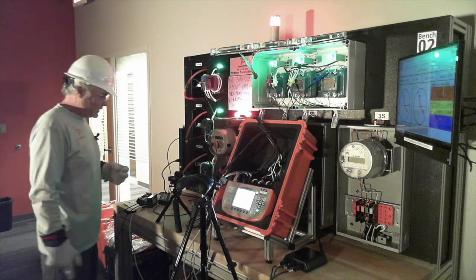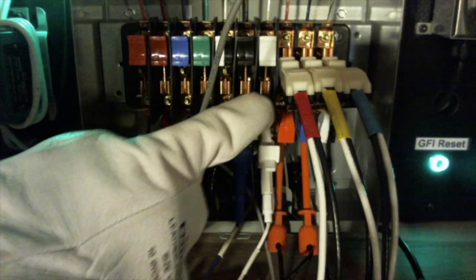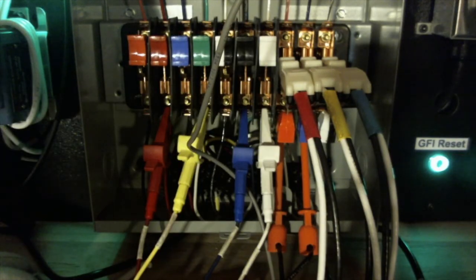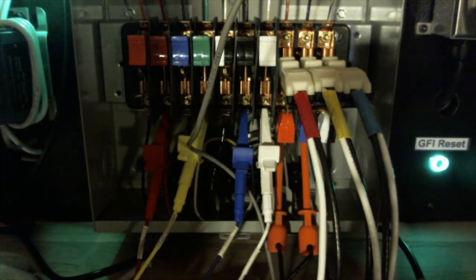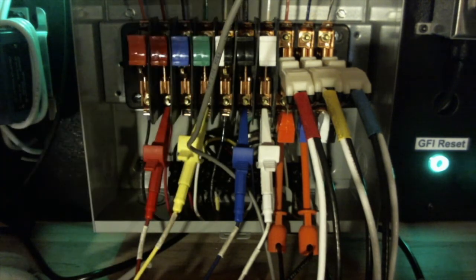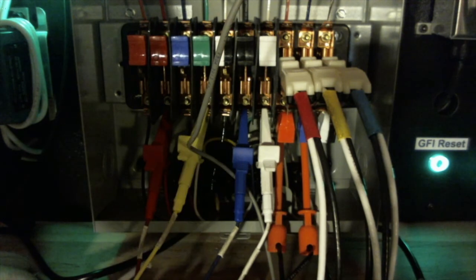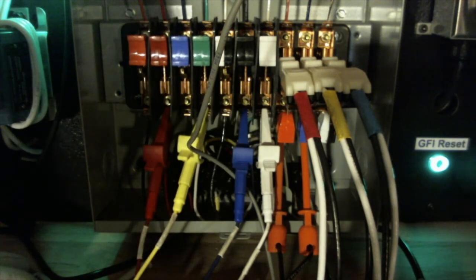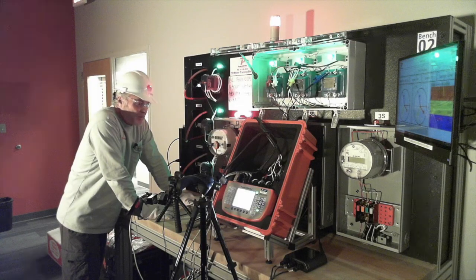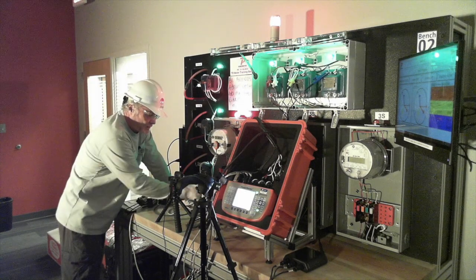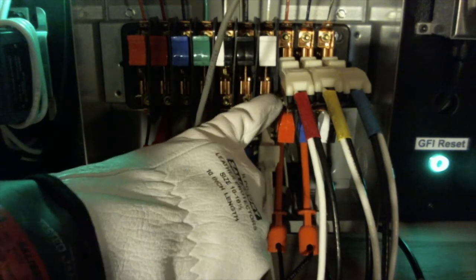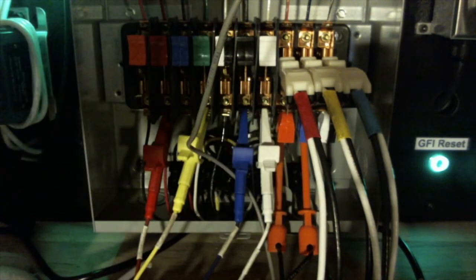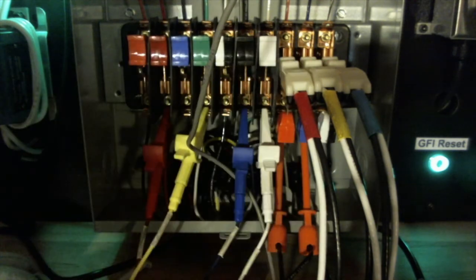So I'm going to move over to here, so I'm going to show you. I'm going to drive with my duck bills. So using the duck bills to drive, we always remember for a PowerMaster and for these duck bills, it's in the white, out the black, or out the black and in the white. When you're just reading that secondary current, it's in the white, out the black. But when I'm driving my current there, it's out the black and in the white. I'm driving the current out the bottom of my duck bills here, out the black, and I'm going to drive it through this meter and come back through the white and back to my test kit.